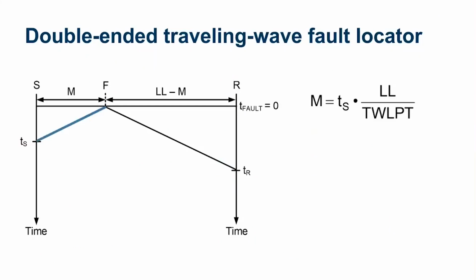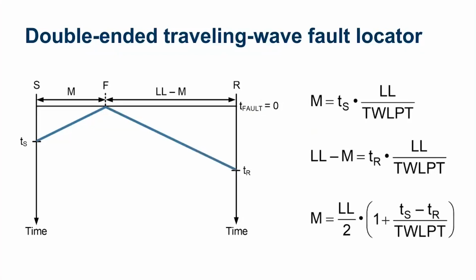And terminal S can calculate the fault location based on the arrival time times the line length divided by the traveling wave line propagation time. Now, a wave is going to be launched from that same fault point to terminal R, and we can calculate the line length minus M. It's going to be equal to the arrival time at terminal R times the line length over the traveling wave line propagation time. So we can solve these equations for M, and what we're going to find is that M is going to be equal to the line length divided by 2 times the quantity of 1 plus the arrival time at terminal S minus terminal R over our traveling wave line propagation time.